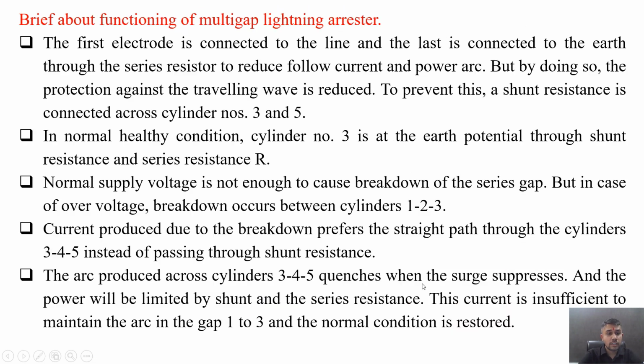The current produced due to the breakdown prefers the straight path through the cylinders. The arc produced across cylinder 3, 4 and 5 quenches when the surge suppresses, and the power will be limited by shunt and series resistance. This current is insufficient to maintain the arc in gap 1, 2, 3 and the normal condition is restored. This is how the multi-gap lightning arrestor functions at the time of switching surge or lightning surge.